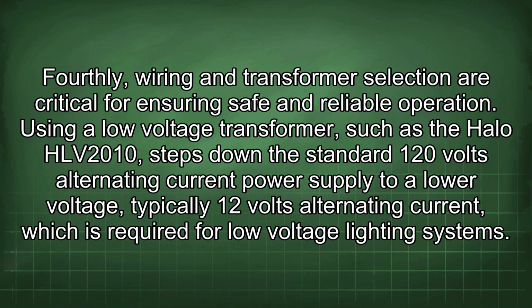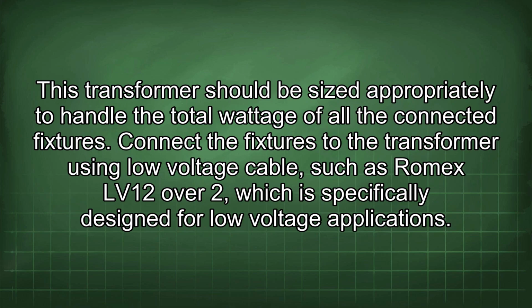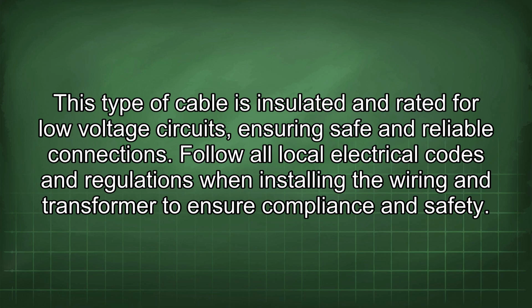Fourthly, wiring and transformer selection are critical for ensuring safe and reliable operation. Using a low-voltage transformer, such as the Halo HLV 2010, steps down the standard 120 volts alternating current power supply to a lower voltage, typically 12 volts alternating current, which is required for low-voltage lighting systems. This transformer should be sized appropriately to handle the total wattage of all the connected fixtures. Connect the fixtures to the transformer using low-voltage cable, such as Romex LV12/2, which is specifically designed for low-voltage applications. This type of cable is insulated and rated for low-voltage circuits, ensuring safe and reliable connections. Follow all local electrical codes and regulations when installing the wiring and transformer to ensure compliance and safety.